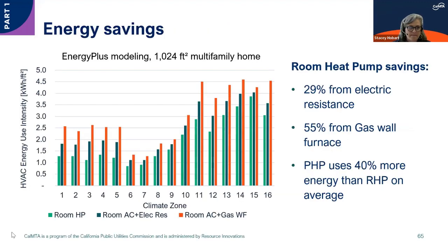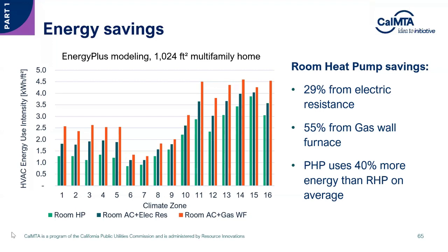Randall, does that answer? Yeah. I was just going to say, most of the analyses I've seen show that any new heat pump, or AC unit for that matter, is going to be higher efficiency than what it replaces. Because if the AC unit or existing heat pump unit is at the end of its useful life, it has a lower efficiency, not necessarily through degradation, although that's a key aspect of it, but just because it was purchased at a time when the minimum efficiency was a lot lower. So if you're looking at realistic replacement efficiencies on the cooling side, it will increase. And most of the studies I've seen take that into account. We certainly do in our own analyses.